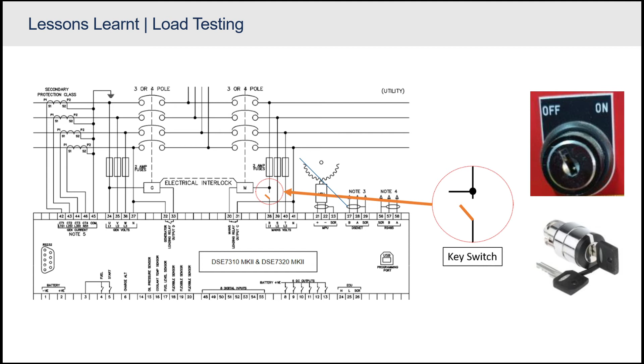One client raised that they don't have a monitoring system in place, so we're not sure how much the generator is running over time. Instead of working on a 250 hours versus a 1 year service interval, since we don't know how many hours it actually ran, let's rather service it once every 6 months. Trying to be very conservative, we did the calculations two ways: look at the actual figures, and also just estimate.